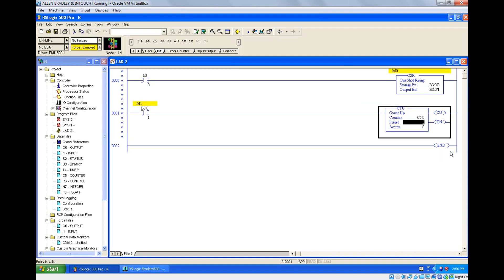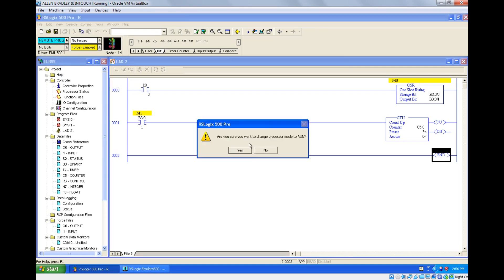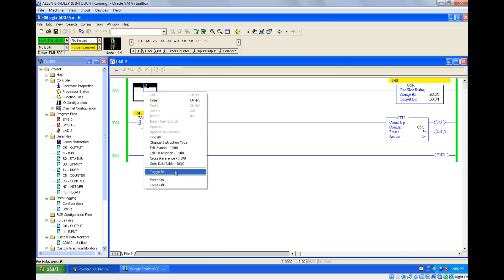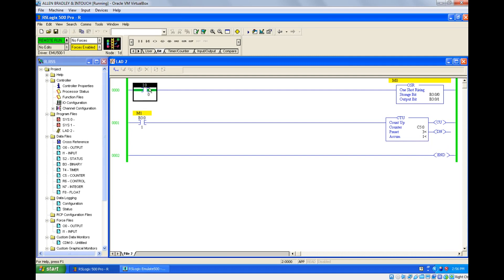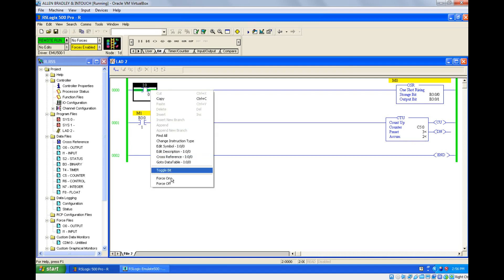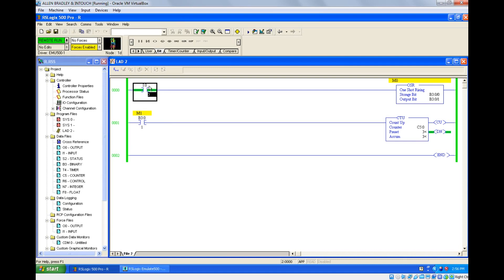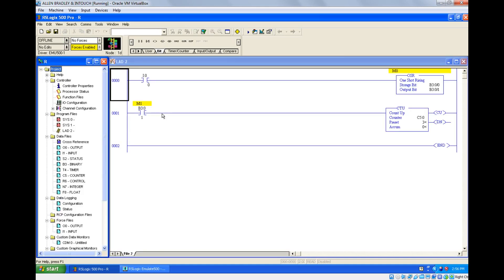I'm using the output bit of one shot rising as input to a counter. Let's check — whenever the input goes from 0 to 1, it will give one pulse. I turn it on — it gives one pulse. If I turn off, nothing happens. Turn on again — it goes from 0 to 1, so it fires again. Count goes to 2, then 3. This is one shot rising — it fires on the rising edge, from 0 to 1.